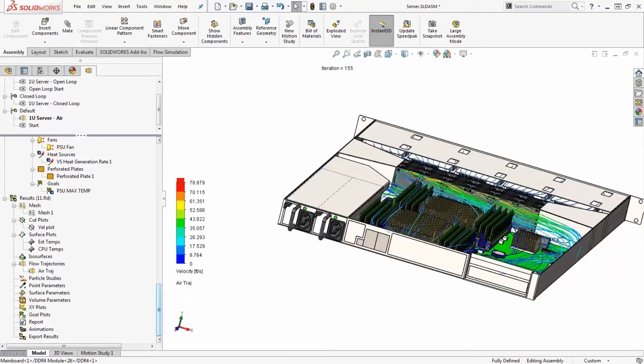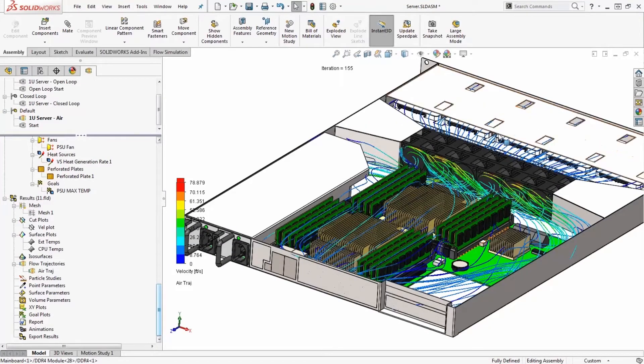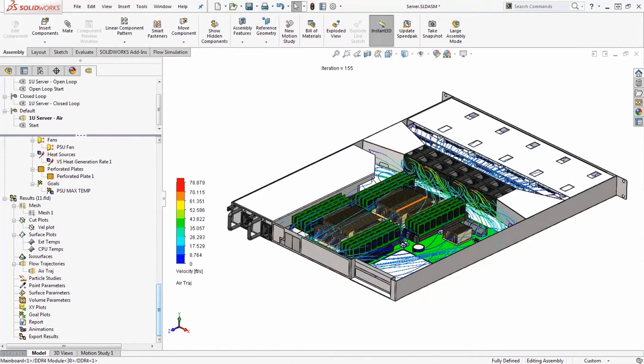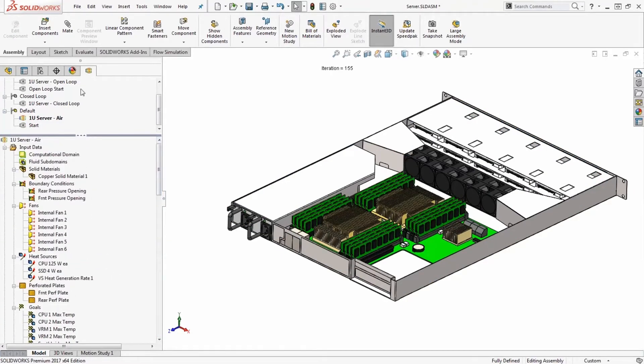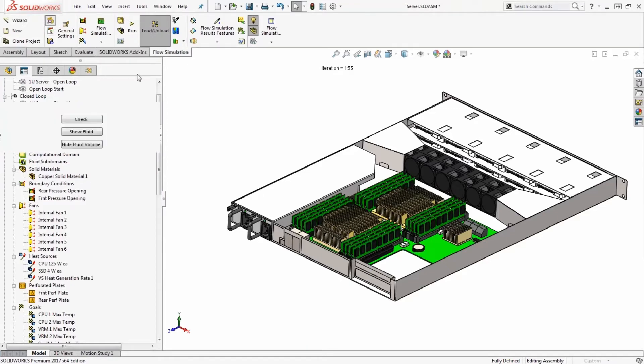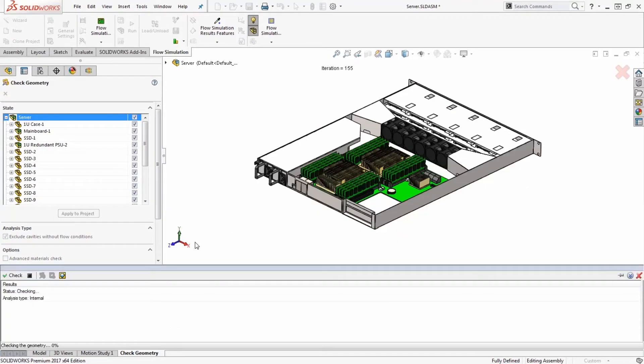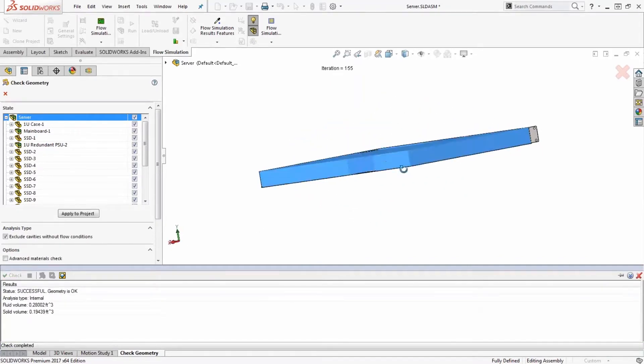In this particular server, there's a bunch of hard drives in the front, an air opening at the front inlet where air is drawn in and blown over all the components, with the only outlets on the back. The power supplies also have fans drawing out air. I set this study up as an internal analysis — that's one of the first things to consider when setting up a flow study. Everything is sealed off to create a closed internal space, which allows the simulation to run more quickly. I can show this internal space using the 'show fluid' option in Flow Simulation.